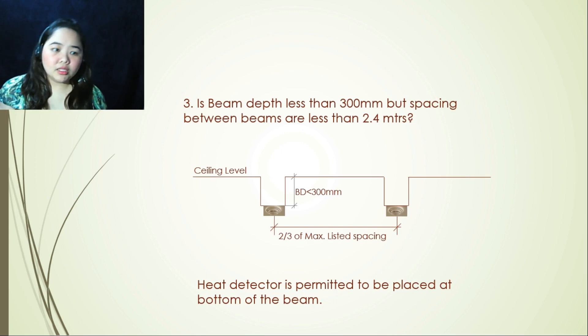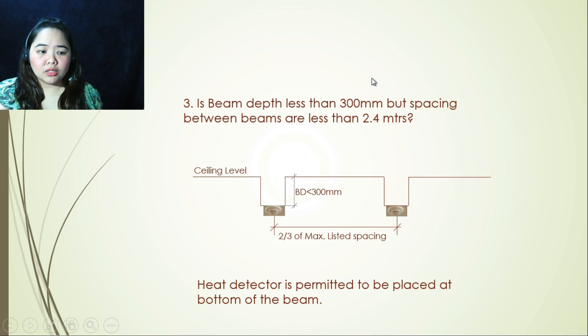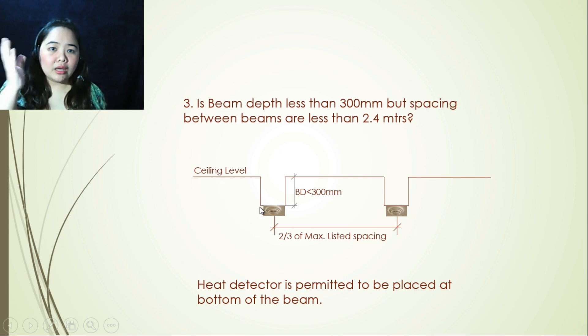Third argument is beam depth less than 300 millimeters, but spacing between beams are less than 2.4 meters. So this is what it looks like. If this is your argument, then smoke detector still can be placed on your ceiling underside, and it's also permitted to be placed at the bottom of the beam, which is still following two-thirds of the maximum listed spacing.